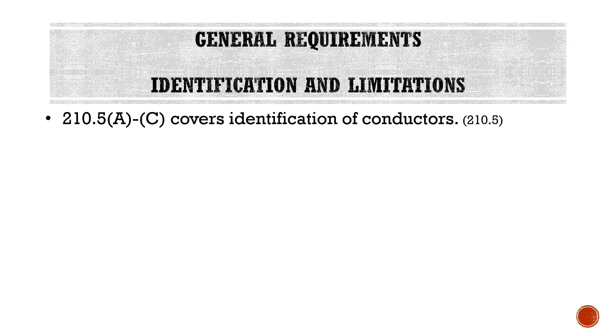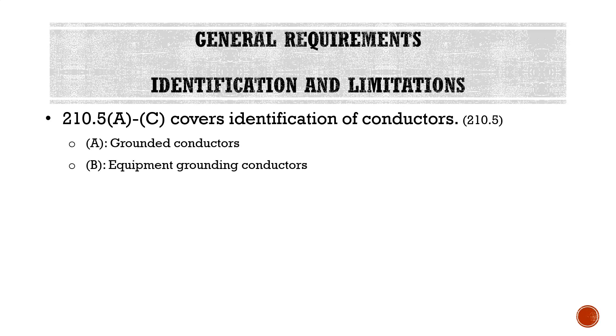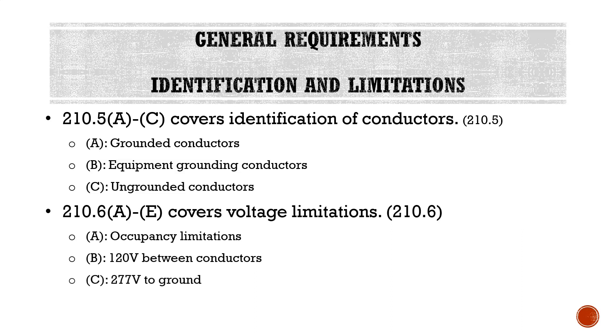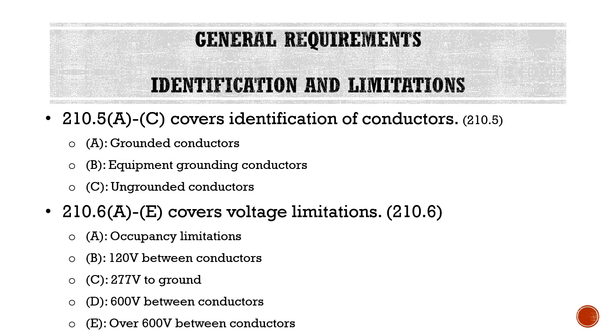Starting into Article 210, some general requirements cover identification and limitations. Sections 210.5A through C cover identification of conductors, including grounded conductors, equipment grounding conductors, and ungrounded conductors. Section 210.6A through E covers voltage limitations for different occupancies: 120 volts between conductors, 277 volts to ground, 600 volts between conductors, and over 600 volts between conductors.